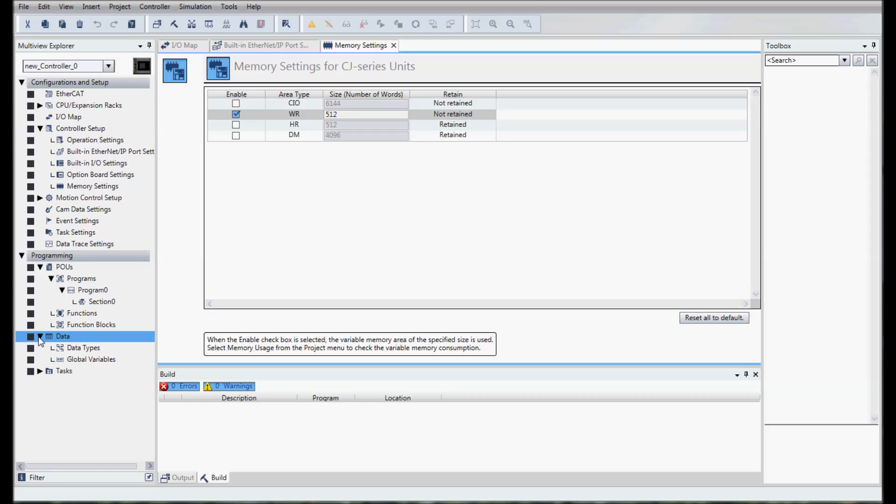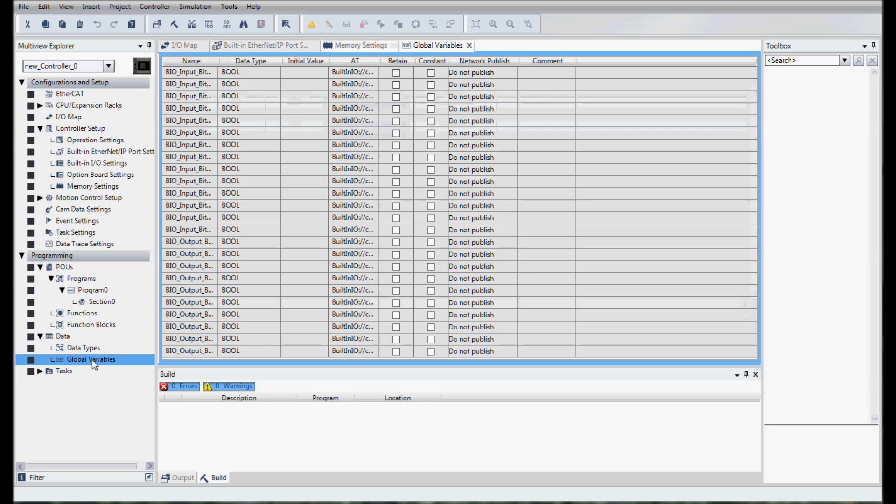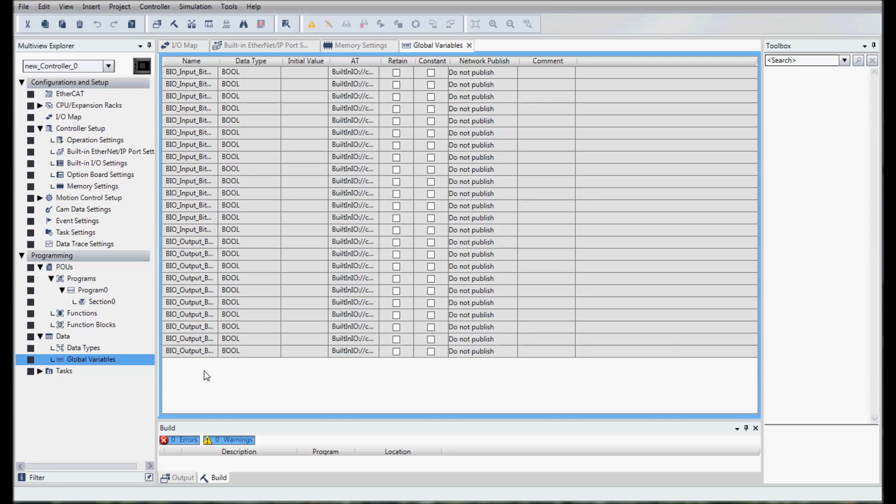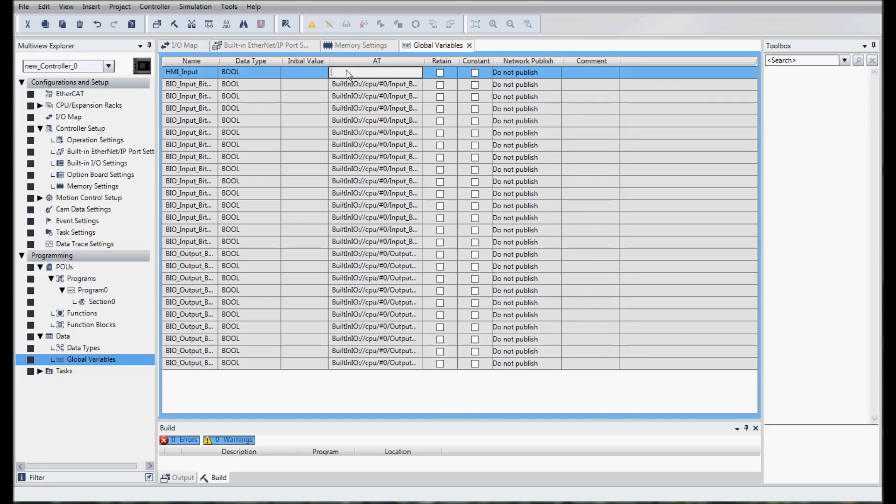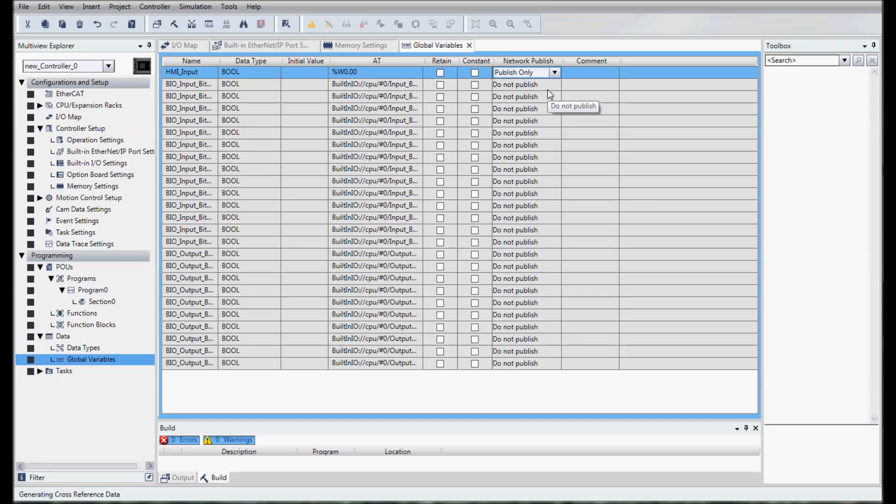Then we will go to our data and then global variables. Already our Bit I/O have all been added here. We can see those. Then we're going to insert. We'll create new and the new one we will call it HMI_input. We'll give it an AT specification of %W0.00 and then we will publish that. What that will do is work relay 0.00 when we press a button on the HMI that bit will turn on and we'll be able to see that in our PLC. We'll now create a couple more variables.